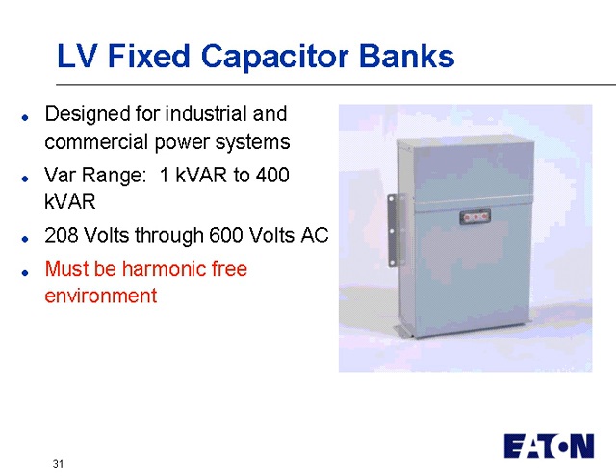So let's look at the actual solutions. Here's a low voltage fixed capacitor bank, and they're typically either wall mounted or floor mounted, and they're in the 100 or 1 kVAR to 400 kVAR range, 208 volt through 600 volt typically.